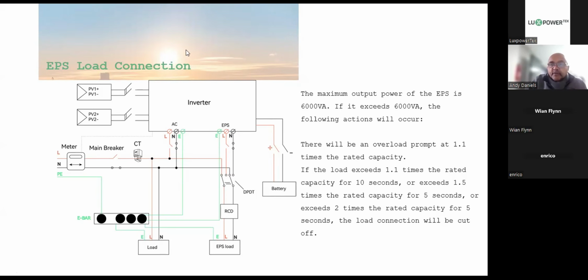Just remember that the maximum output power of the EPS is 6 kVA. If it exceeds 6 kVA, then the following actions will occur. There will be an overload prompt at 1.1 times the rated capacity. If the load exceeds 1.1 times, in other words 6.6 kilowatts, for 10 seconds, or exceeds 1.5 times the rated capacity for 5 seconds, or exceeds double the capacity, in other words 12 kilowatts.